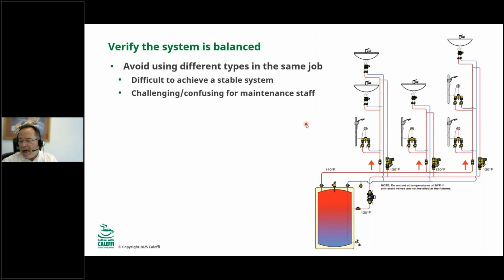I would highly recommend putting in thermostatic balancing valves everywhere. They just solve a lot of problems, right? They'll do what they're made to do with what you have. They will try to control at the temperature no matter what's going on in the system. If they still can't deliver, then you have a bigger problem. Then it's not a balancing valve problem. If you put a thermostatic balancing valve on one riser and it still doesn't work, there's something else going on, like a cross connection or something more serious. But these are a real problem solver. I would recommend replacing everything with the thermostatic.